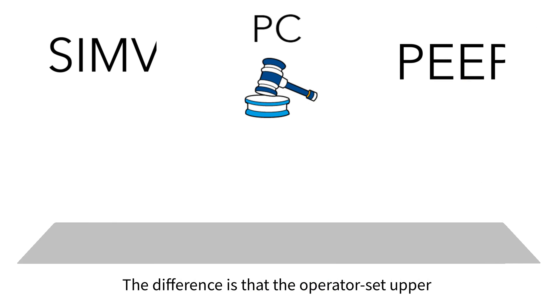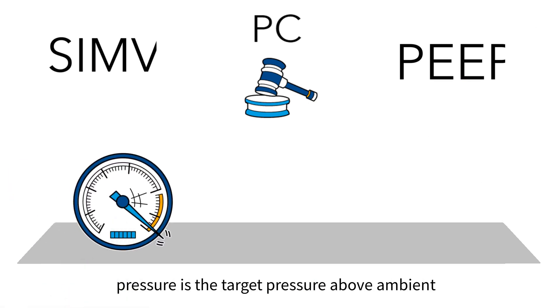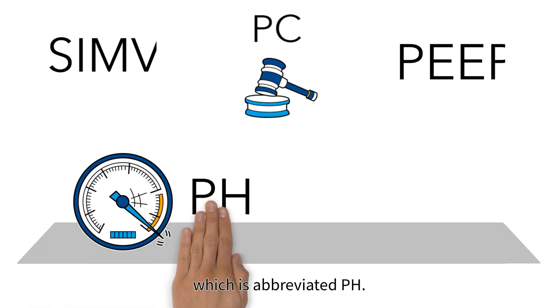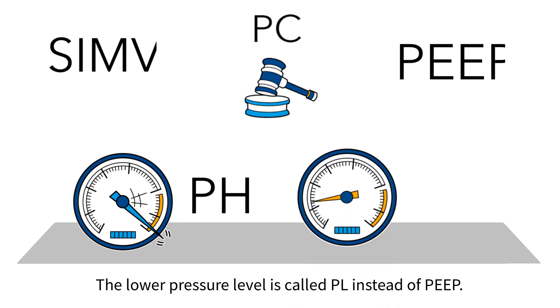The difference is that the operator set upper pressure is the target pressure above ambient rather than above PEEP, and it is called high pressure, which is abbreviated PH. The lower pressure level is called PL instead of PEEP.